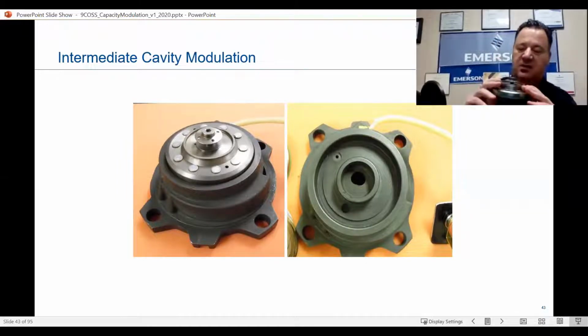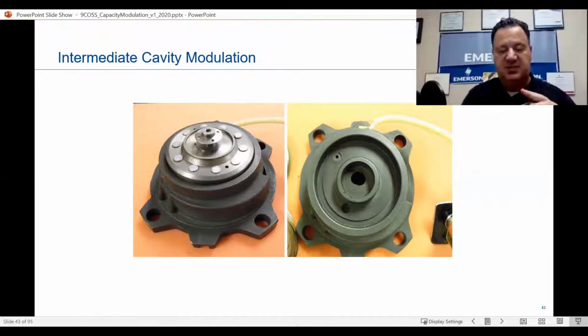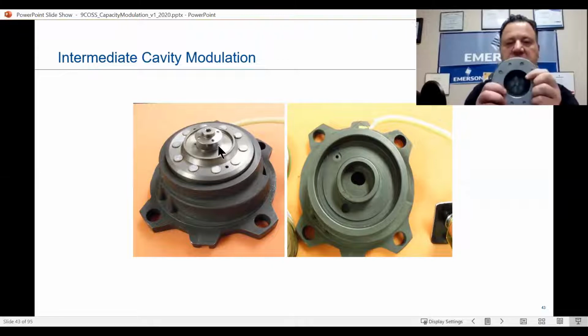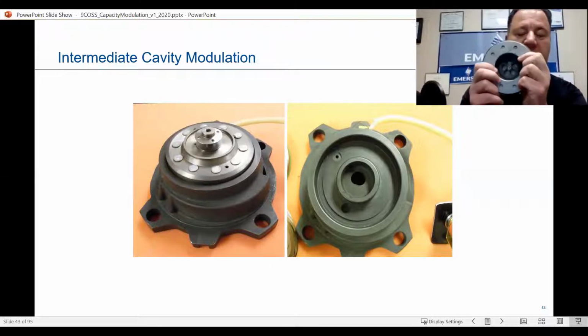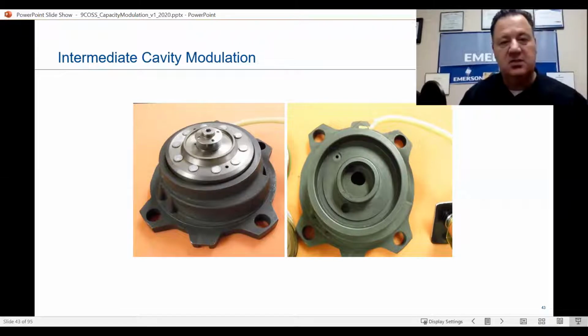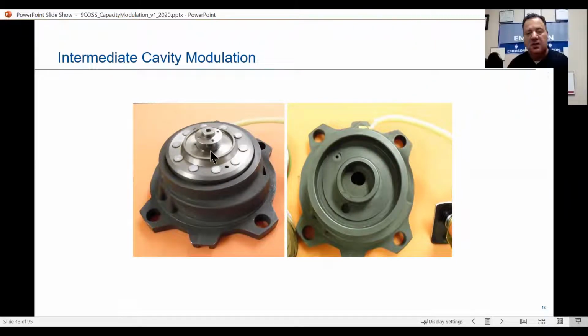In fact, I have one identical here. It's got a little washer here to prevent any kind of expansion gas. It comes through the discharge line right there. There is like a check valve, if you will, but it's really like a flat washer. And you can see the holes here on the bottom. That washer, when it comes down, it blocks those. If the gas should try to come back in from the discharge pressure at the top of the scroll, it stops it. All right. And here's some of that tubing internally I talked about on the larger digital that we're seeing in that copper tubing on the outside.